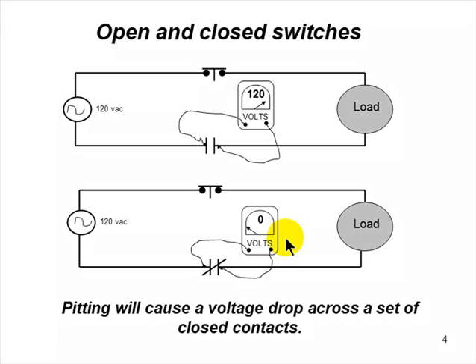How about if I read a voltage drop here? What would that tell me? Well, I got pitting, or dirt, or a June bug got inside the contactor in the summertime at night because that contactor's hot from the current flow through it, and he decided he was going to sleep there that night, and the next morning the condenser contactor pulled in and he got squashed, and you got a voltage drop of 8 or 9 volts across there. Anything that shows a voltage drop means that there's something on those two contacts that connect each other to make this current, give this circuit continuity.